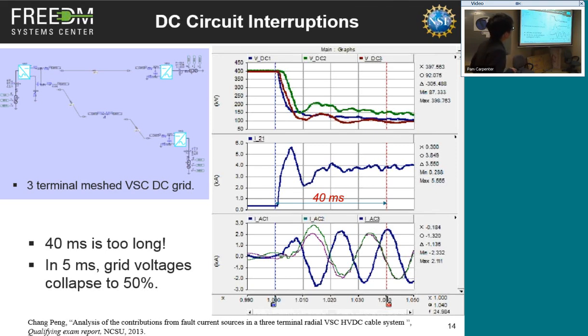Then let's look at what's going on with the DC voltage. We are running this system at 400 kilovolt, and if a fault happens at 1 second, what happens after 40 milliseconds? We see that the voltage at these 3 DC terminals, I'm showing 3 DC terminals, the voltage at these terminals here, drops to, well, it's not really 0, but it's 100 kilovolt.